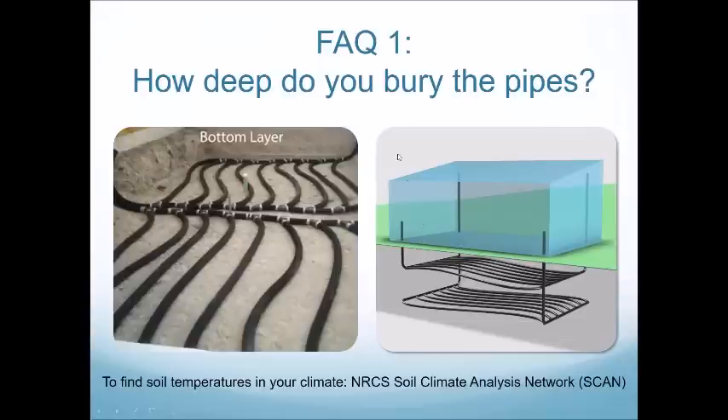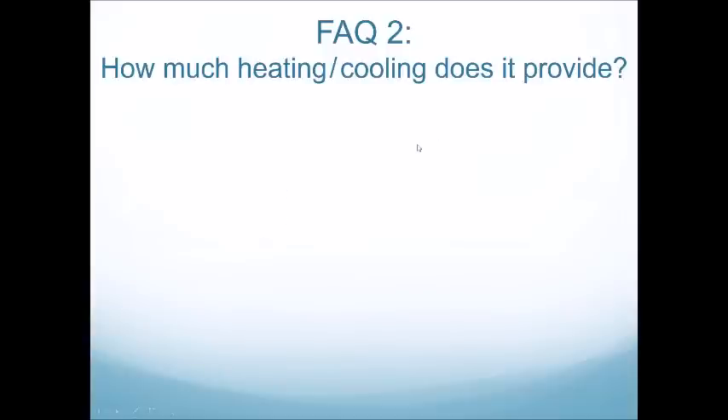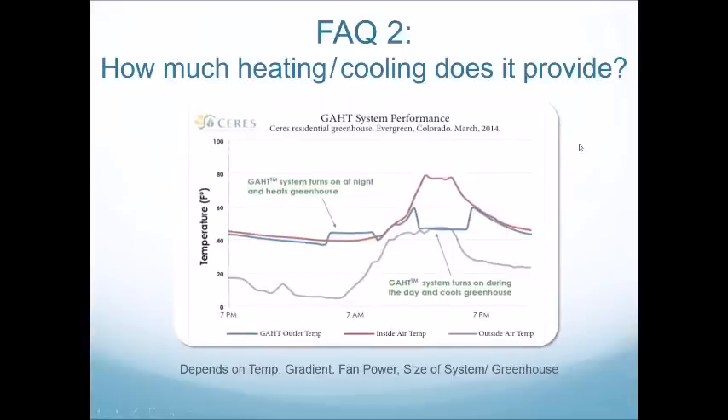Soil temperatures vary with climate, and the NRCS Soil Climate Analysis can be a good source to figure out your soil temperatures. The next question is: how much heating and cooling does a GAHT system provide? This really depends on where you are — the temperature gradient inside the greenhouse versus the ground, which is controlled by climate, as well as fan power and the size and shape of your greenhouse. Looking at this graph, done with thermocouples in Evergreen, Colorado in March, there are three measurements: GAHT outlet temp in blue, inside air temp in red, and outside air temp in gray.